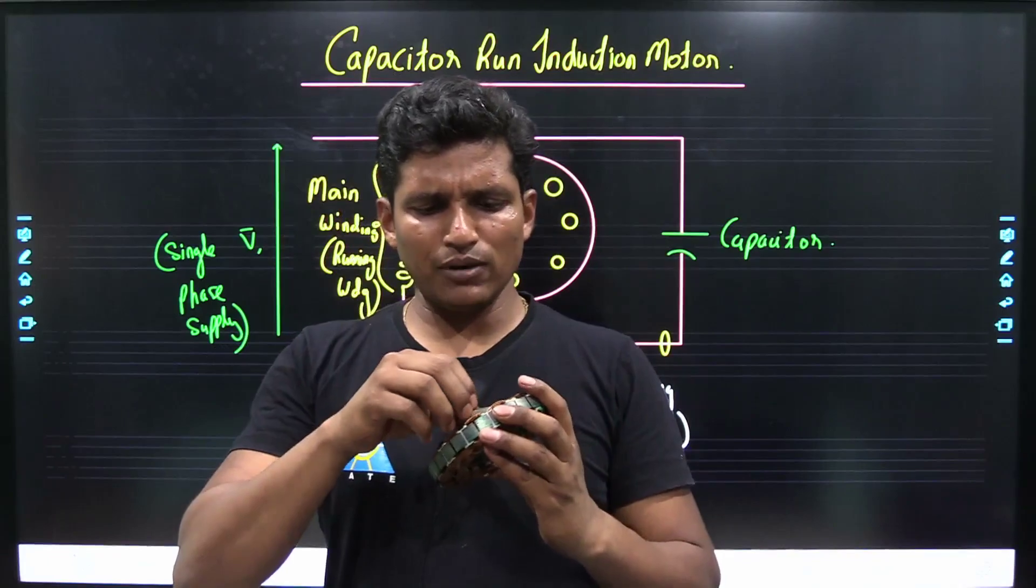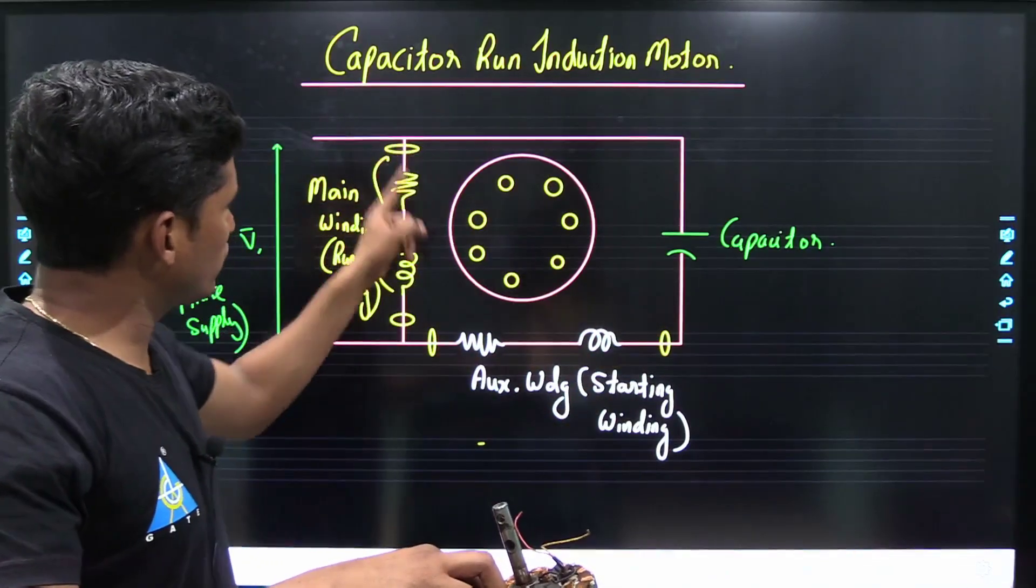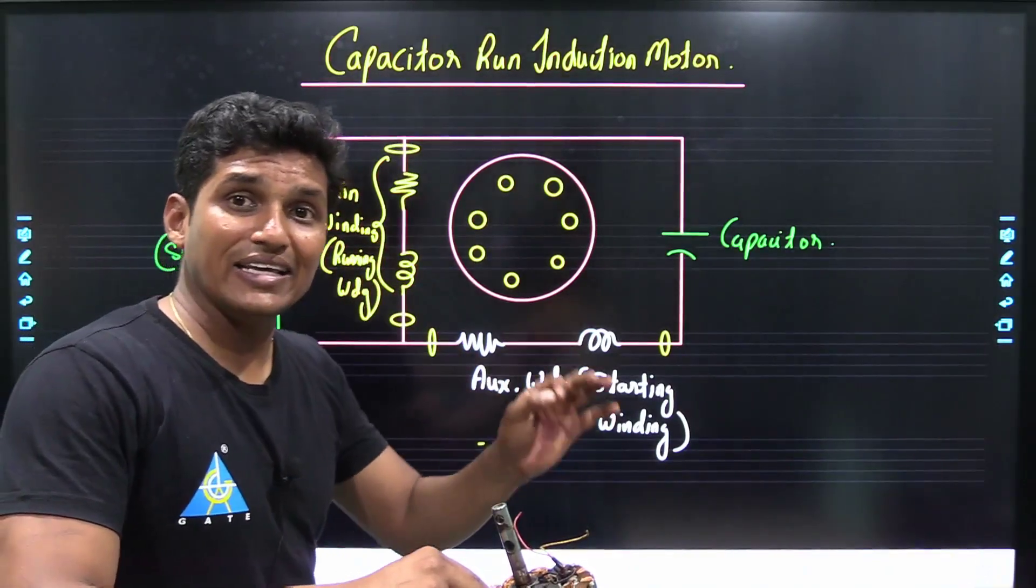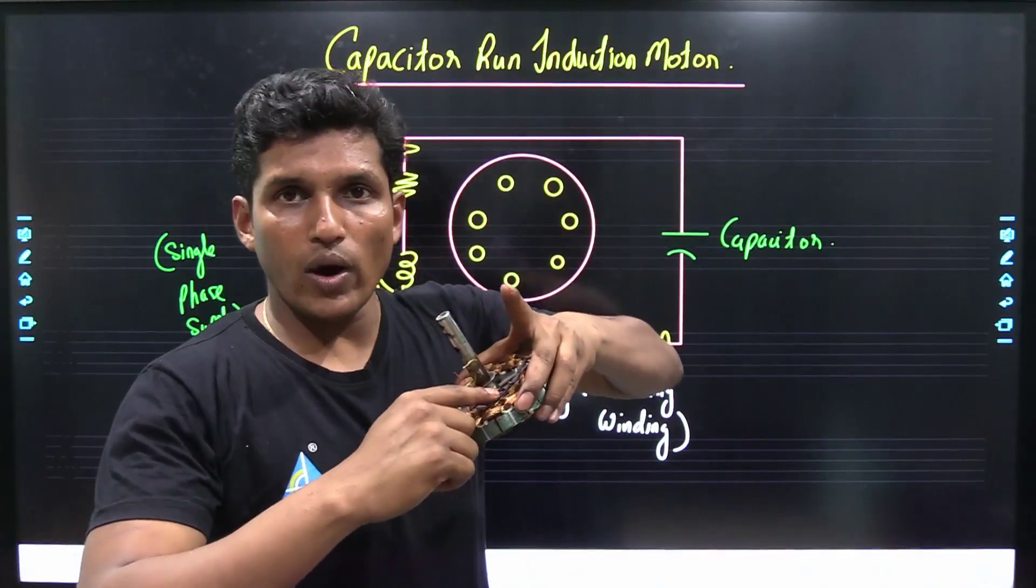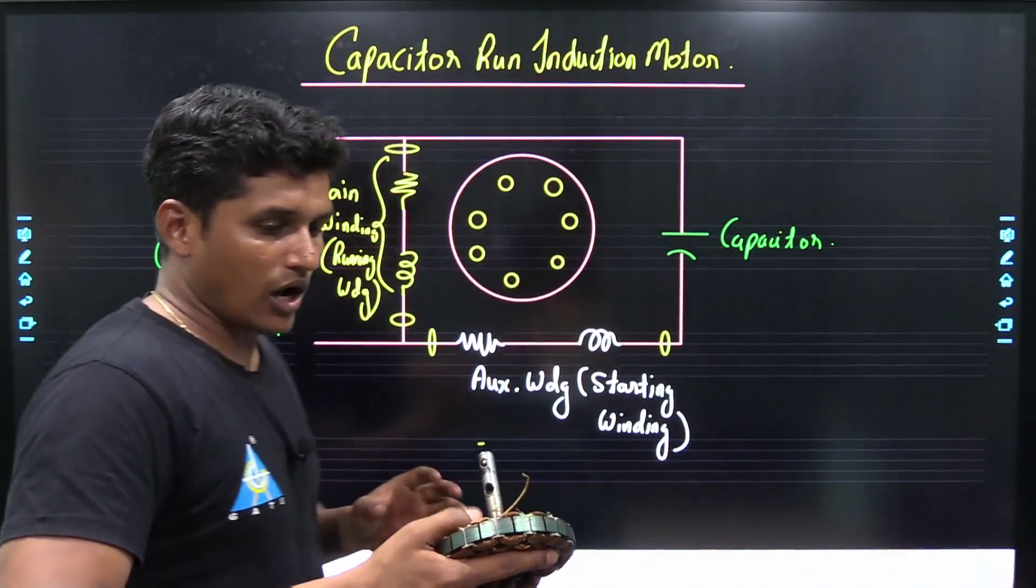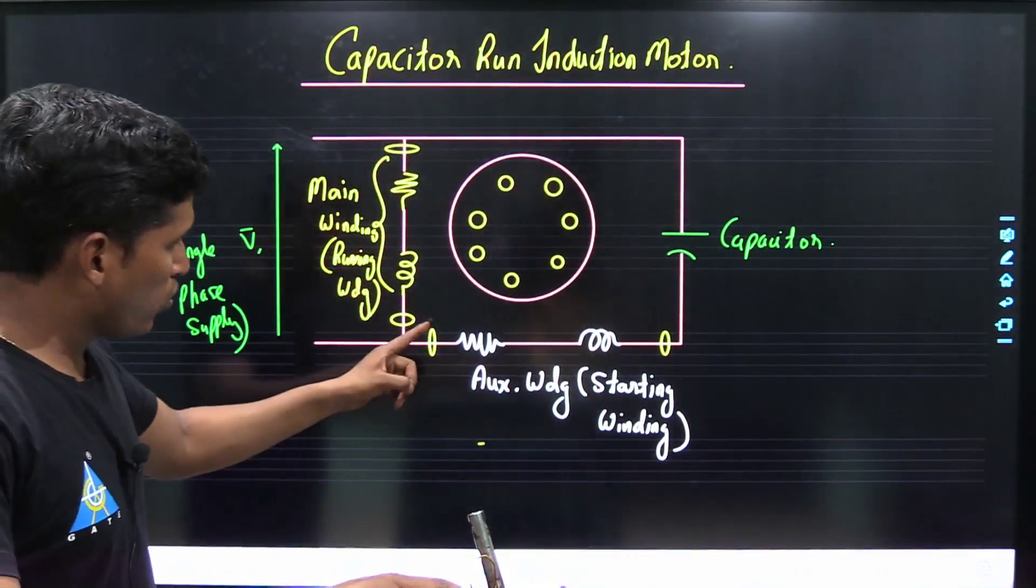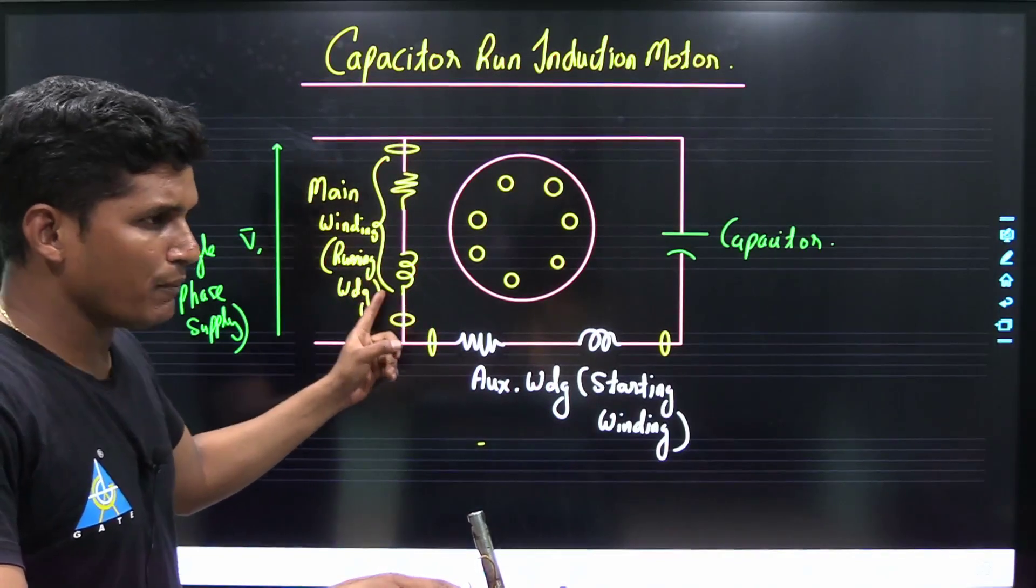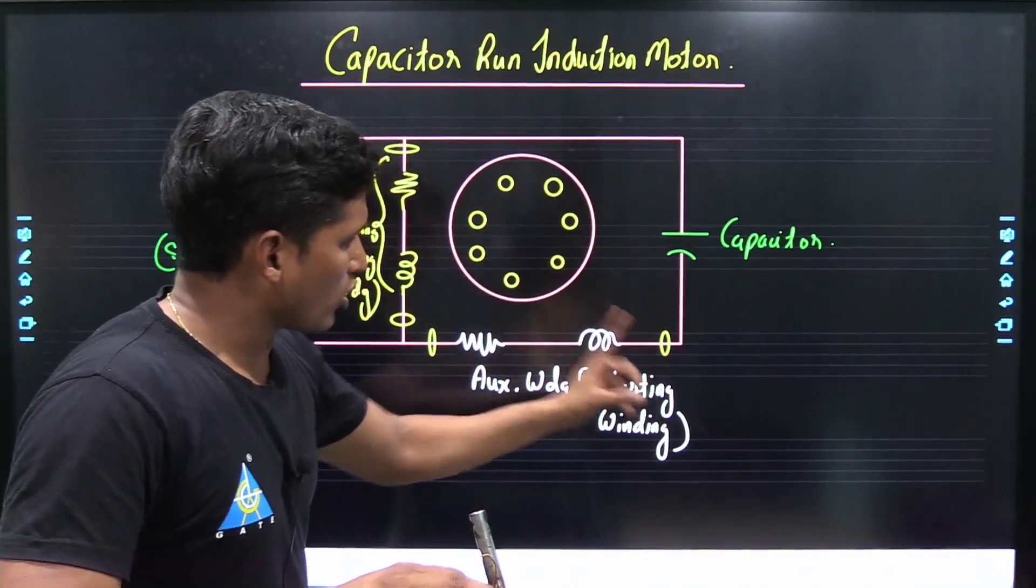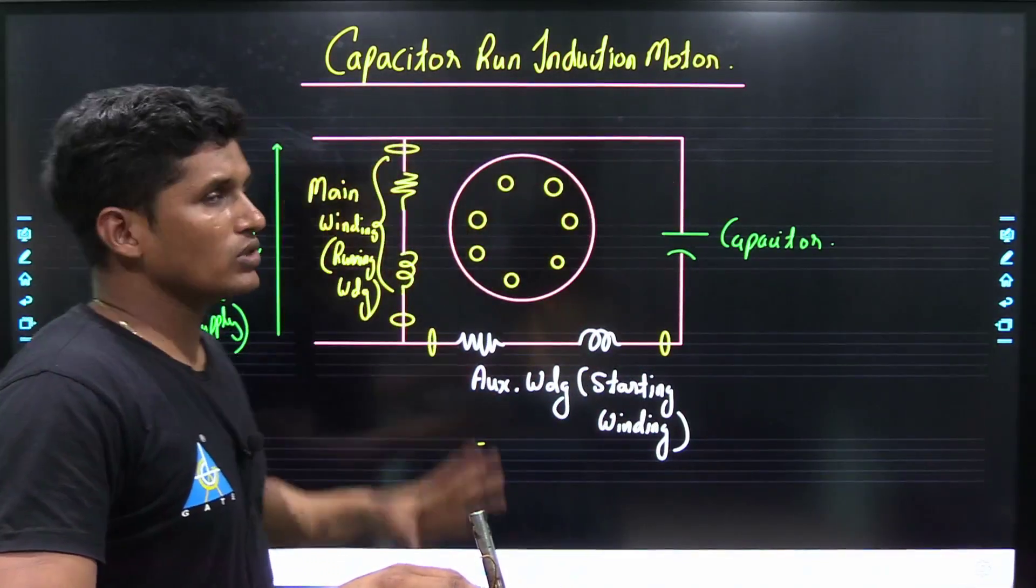In this, three terminals are available at the outside. Two terminals of main winding and auxiliary winding are made inside the winding and only one terminal is made outside. Now, out of these three terminals, one terminal which is the junction of the main winding and auxiliary winding is directly connected to the supply. Whereas the other two terminals, one of the auxiliary winding and one of the main winding, the auxiliary winding terminal is connected to the capacitor and with the help of the capacitor it is connected to the supply.